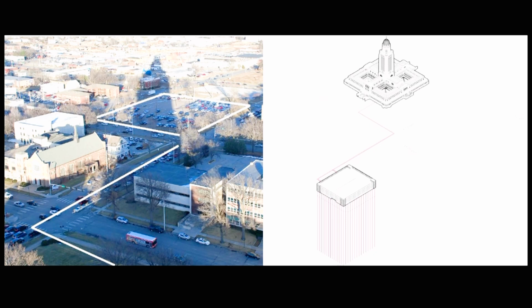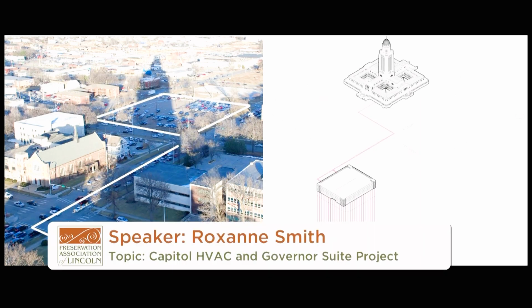The state had a parking lot that we could use as a well field, and this shows the well field and the route to the Capitol. On the right, you can see the Capitol. You can see the pipes leading to the well field from the building, and then you can see the wells. Within the well field, there are 225 wells, 675 feet deep. When we pull heat out of the building in summer for air conditioning, we will raise the temperature of the ground beneath that well field 4 degrees.